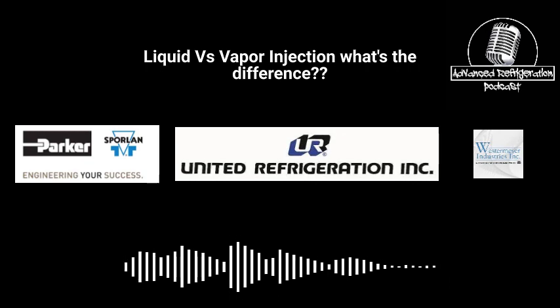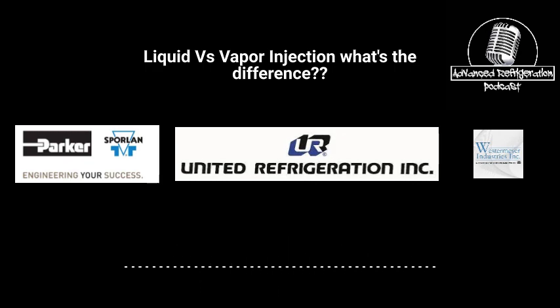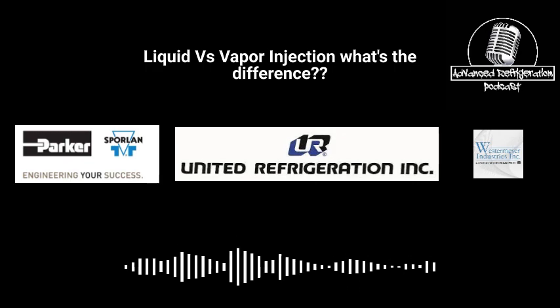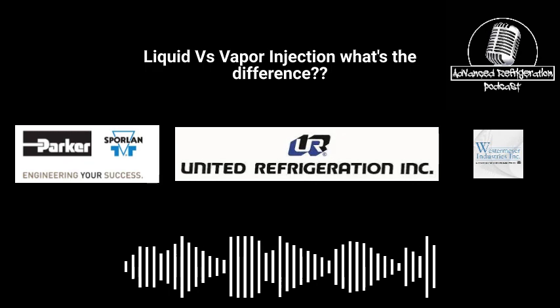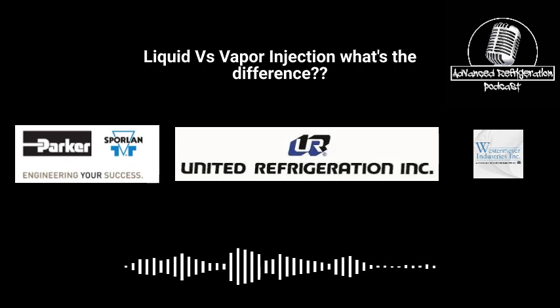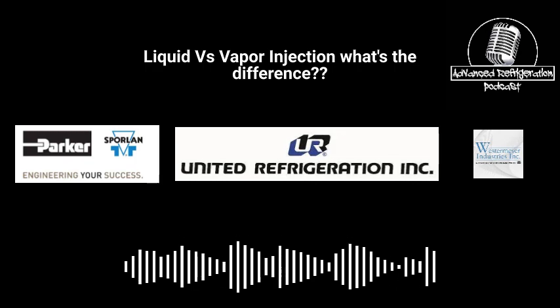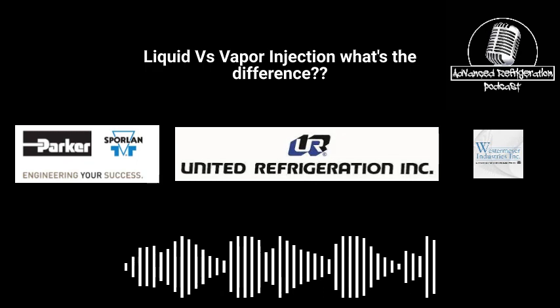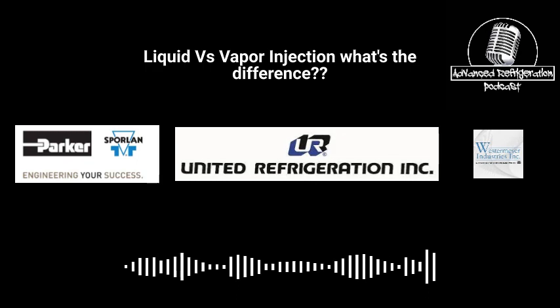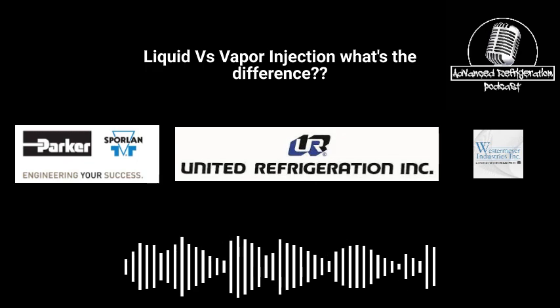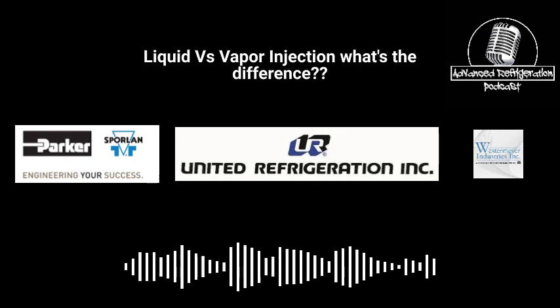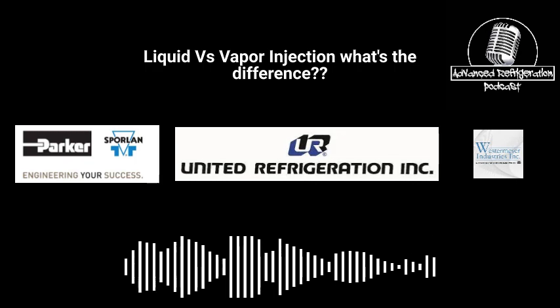And usually they're overheating. I don't want to see a good compressor over 190, which, obviously with these new glides and we're running 448 and we're running higher compression ratios, you're going to get that high. There's pretty much no way around it. Even with vapor injection or liquid injection, you're still going to get that high. So that's where keeping your superheats down at the rack is imperative. You don't want to be running high superheats. You want to keep that post defrost. If you're using hot gas, you want to keep that post defrost hot gas from overheating stuff.